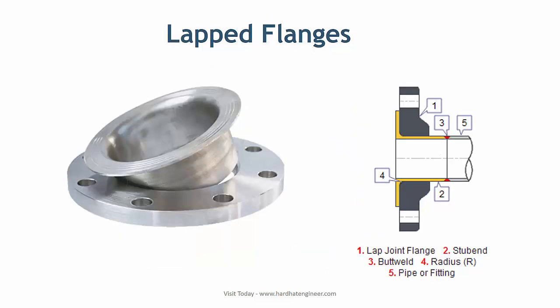Lap flange has two components: a stub end and a loose backing flange. The stub end is butt welded to the pipe and the backing flange freely moves over the pipe. The backing flange can be of a different material than the stub end material — normally carbon steel — to save the cost of the overall piping. Lap flange is used when frequent dismantling is required and the space is constrained.